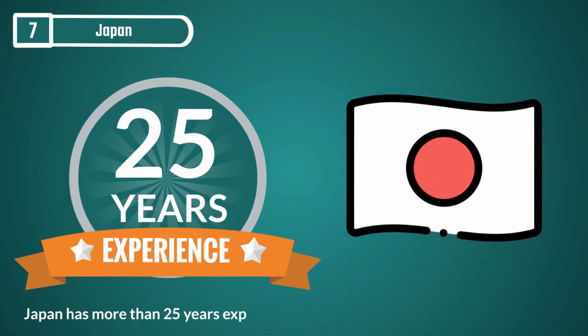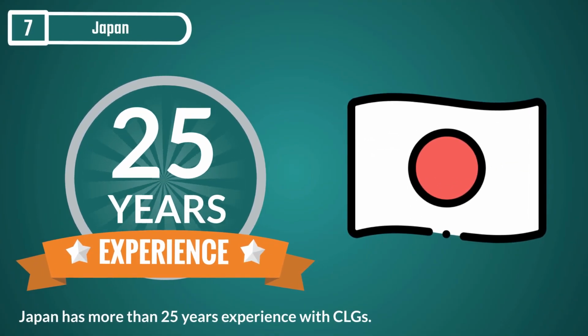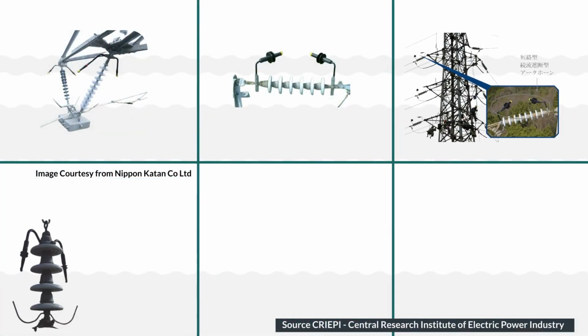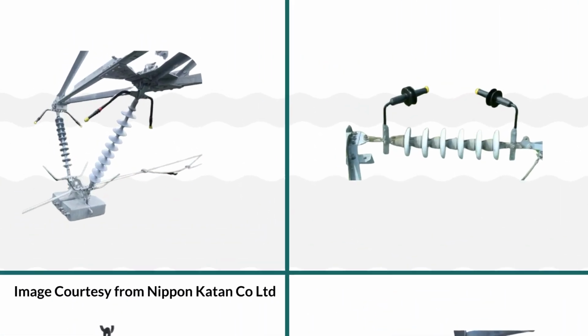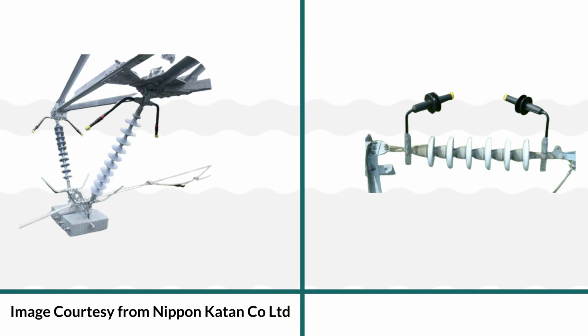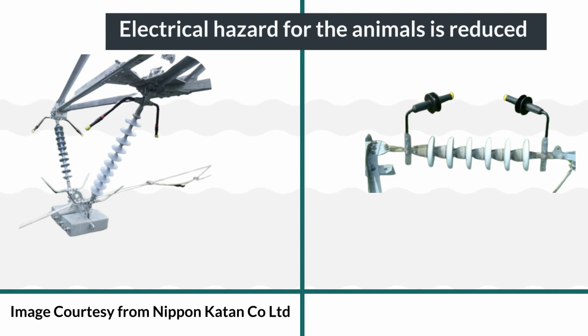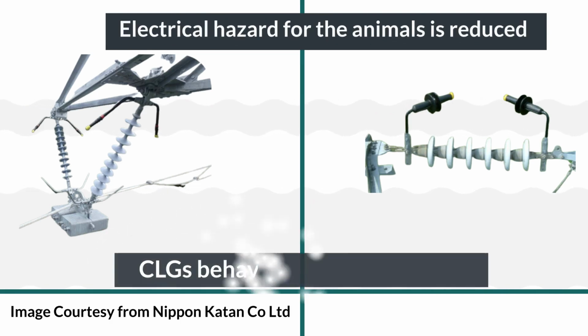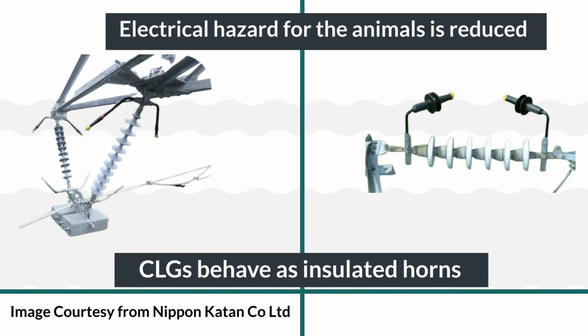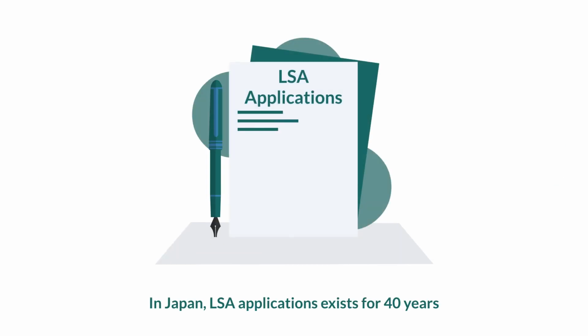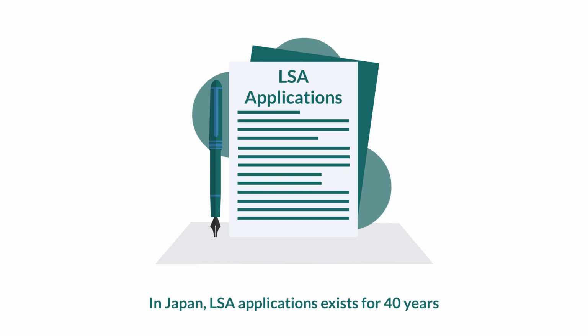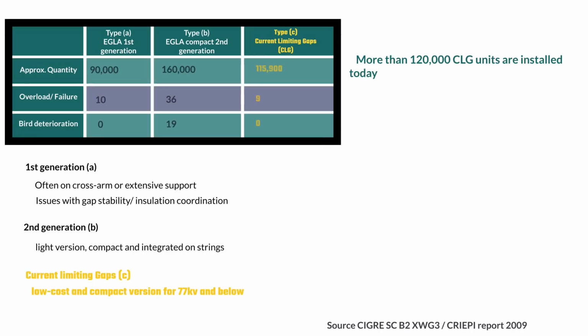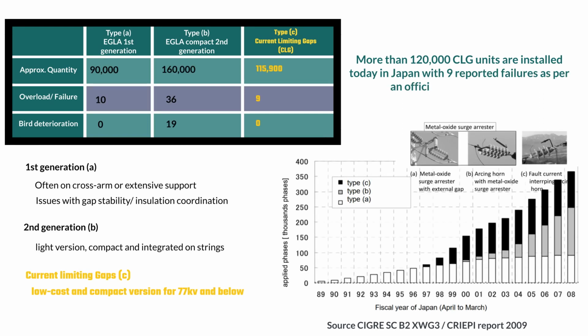Japan. Japan has more than 25 years of experience with CLGs. They also recommend the use of CLGs as bird protection equipment. Indeed, when the conventional arcing horns of the insulator strings are replaced by CLGs, the electrical hazard for the animals is reduced, or even eliminated, because the CLGs behave as insulated horns. In Japan, LSA applications exist for 40 years. They actually claim the first installation in history. More than 120,000 CLG units are installed today in Japan, with 9 reported failures, as per an official report from 2009.